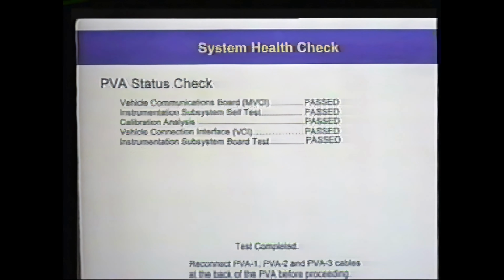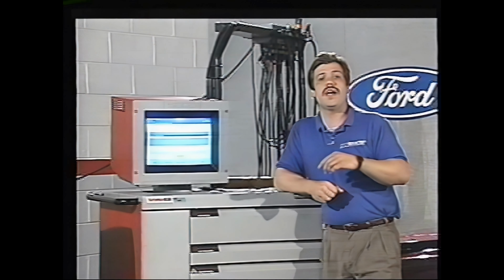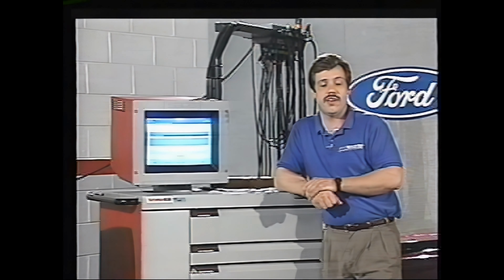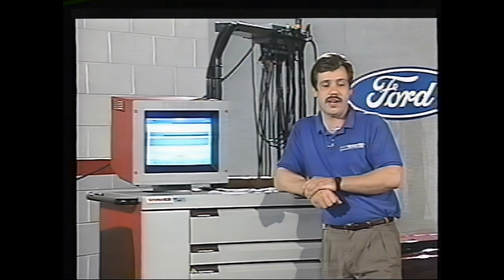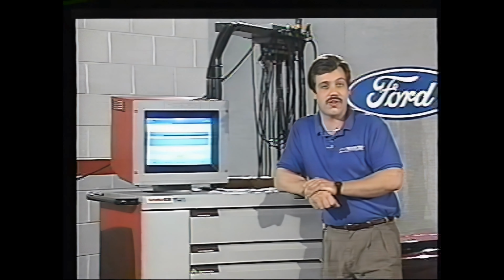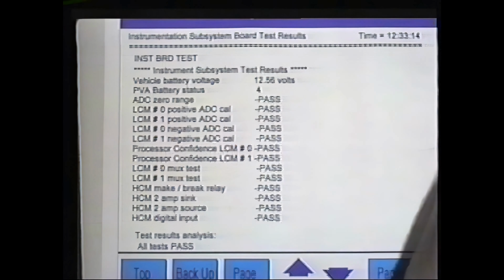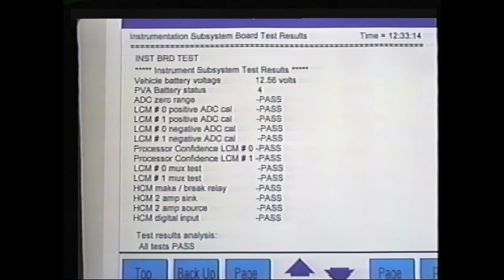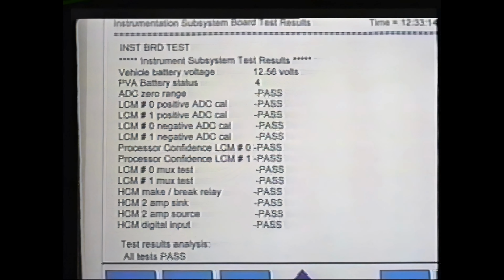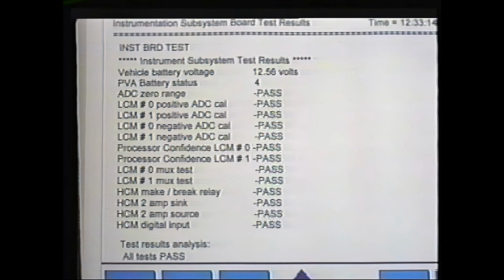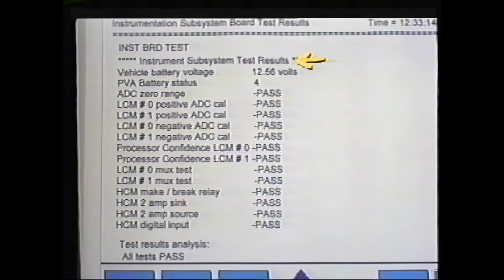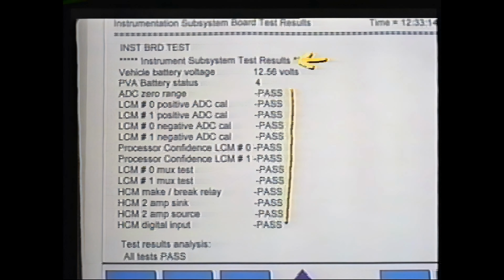If you have a failure there, go back into the log file to see exactly what failed before calling the tech hotline. This screen shows the instrument subsystem test results, the major addition for the extended health check, with the right-hand margin showing all routines and whether they passed or failed.